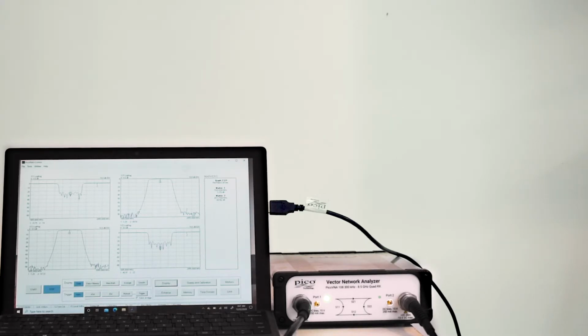Notice in the diagram, to perform calibration, cables supplied by the manufacturer are run from port 1 and port 2 in the module to the device under test. PICO supplies two types of connectors that attach to the cables. They call them kits. If the insertable device under test has one or two male connectors, use female cables and identical male kits for both ports.